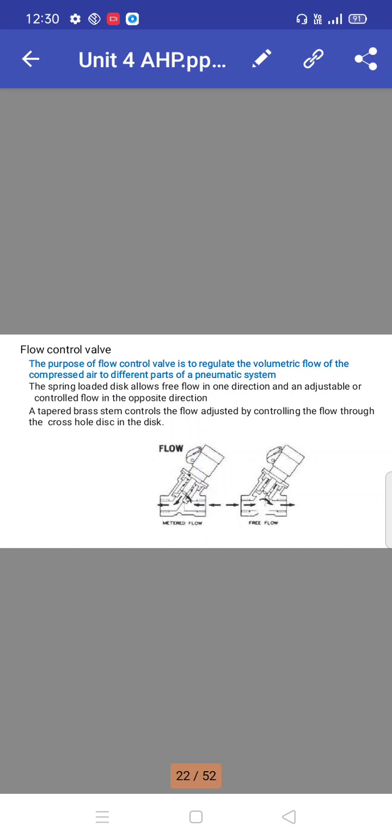Flow control valve: the purpose of a flow control valve is to regulate the volumetric flow of compressed air to different parts of the pneumatic system. The spring-loaded disc allows free flow in one direction and adjustable or controlled flow in the opposite direction. A tapered brass stem controls the flow by adjusting the cross hole in the disc.